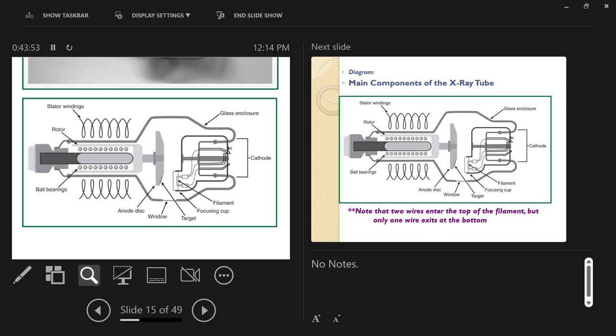Earlier cathode ray or Crookes tubes from the late 1800s used an inert gas instead of a vacuum, as it was easier to achieve. Nowadays all x-ray tubes are vacuum sealed. If the bearings fail, you can't just replace them — the whole tube must be replaced, like an incandescent light bulb where you can't replace just the filament. Once built and sealed, it's non-serviceable.